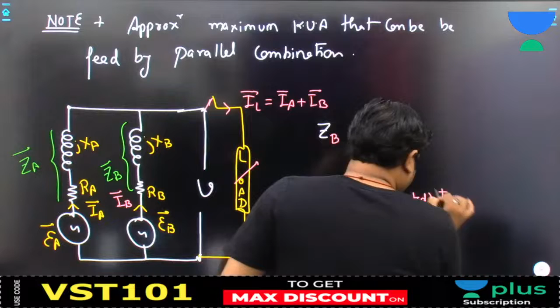Please observe, the maximum KVA that this combination can feed is the rated KVA of the transformer that gets overloaded first plus the operating KVA of the other transformer.